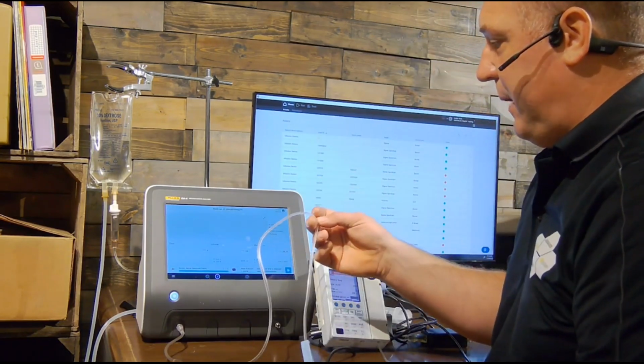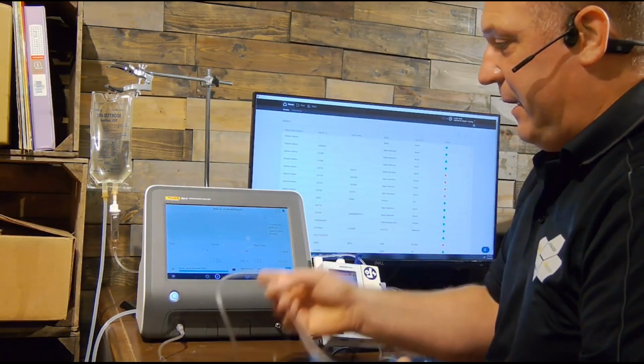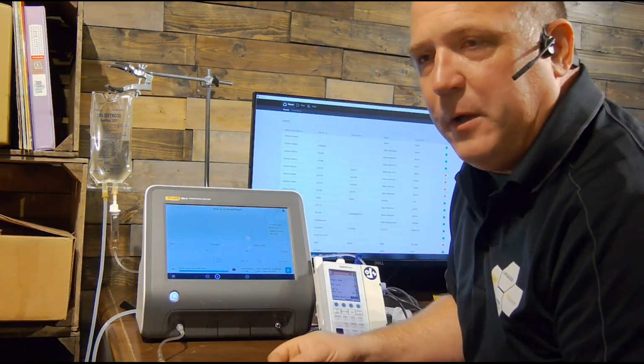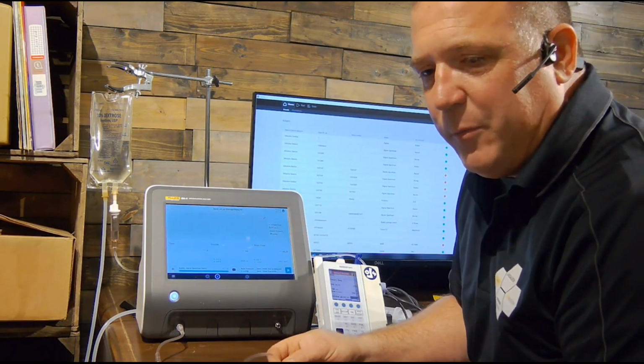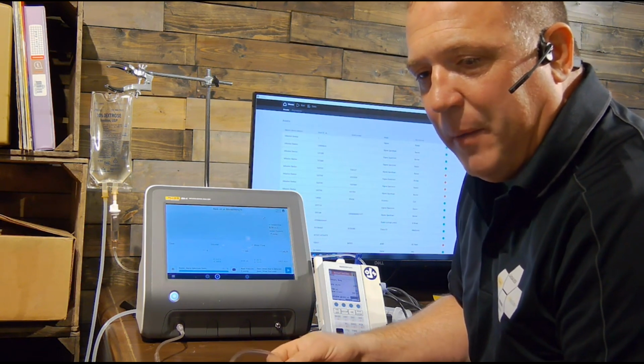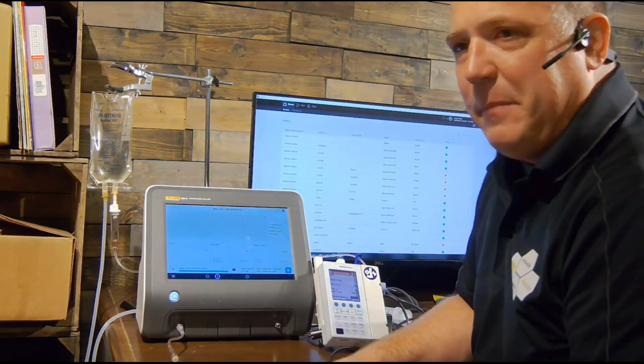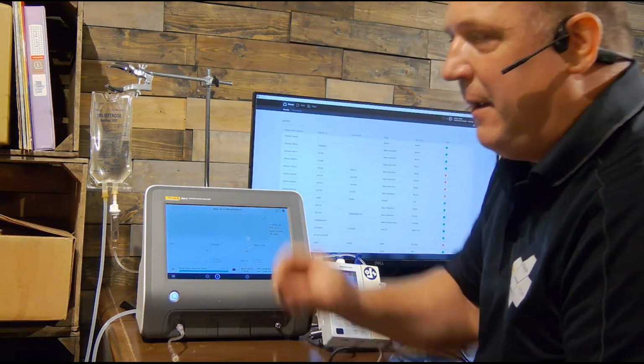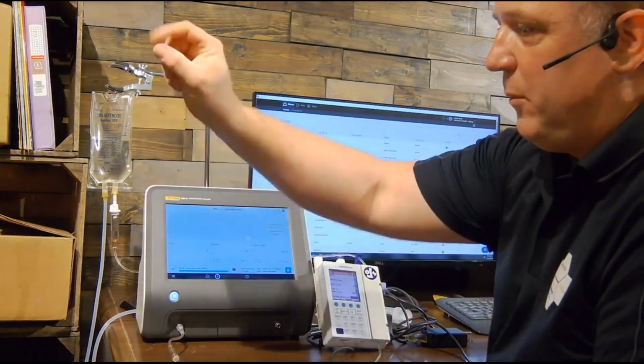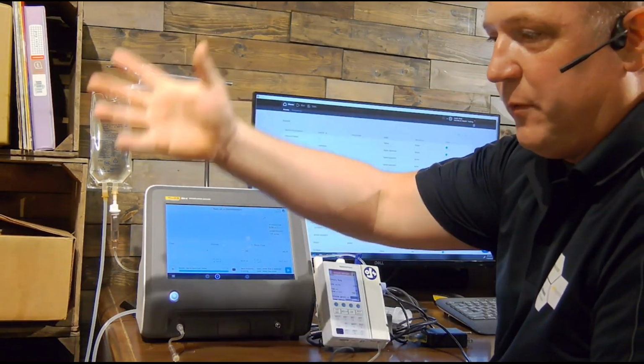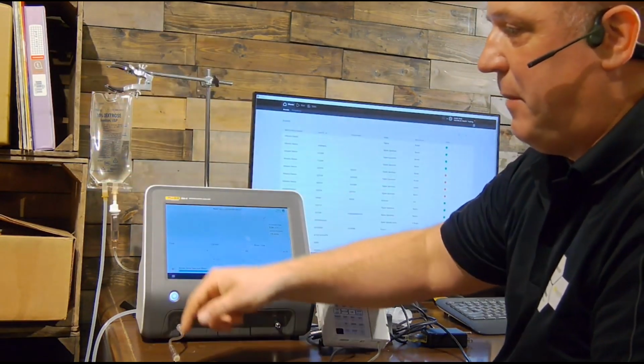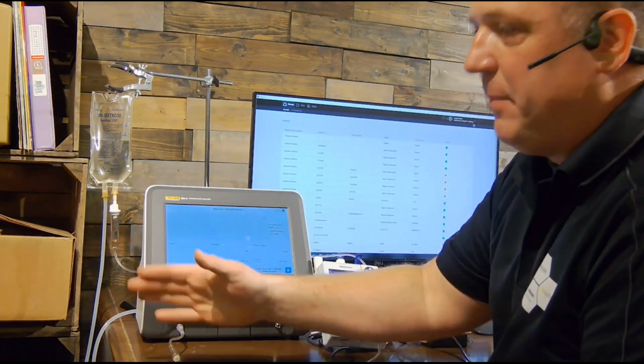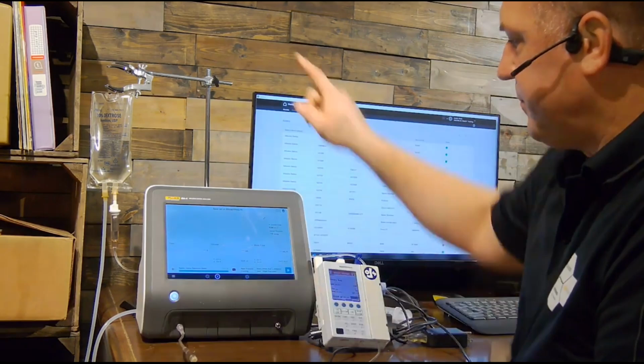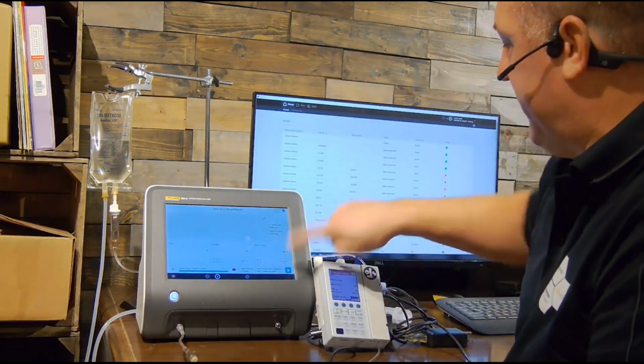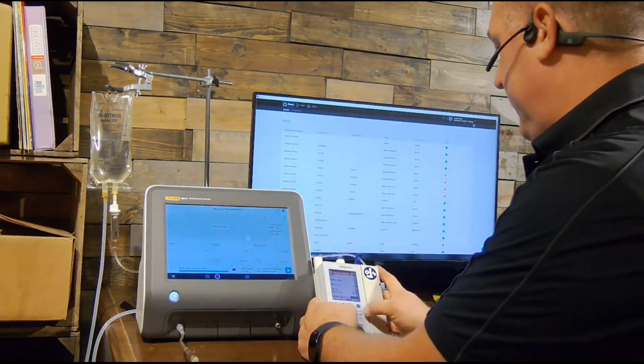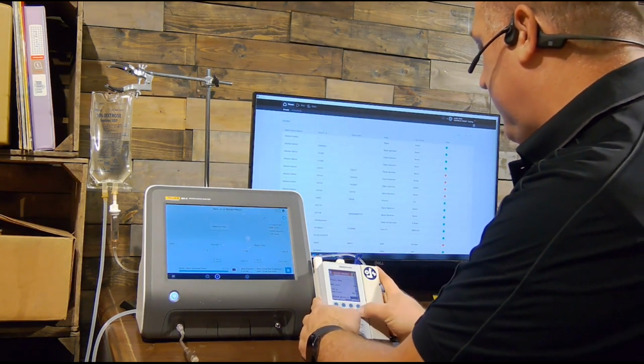So the occlusion pressure took care of that. The other thing I need to mention is volume is volume. So with the IDA-5, we used to get air bubbles from the solution. Here it doesn't matter so much. In the IDA-5, we had that glass pipette. You had to watch those air bubbles because volume wasn't seen. So this is the piston-driven stepper motor. Even if it has an air bubble, it'll still measure it as volume. All right, now that I'm set up, I'm going to go ahead and push play here. And I'm going to hit OK here and run.